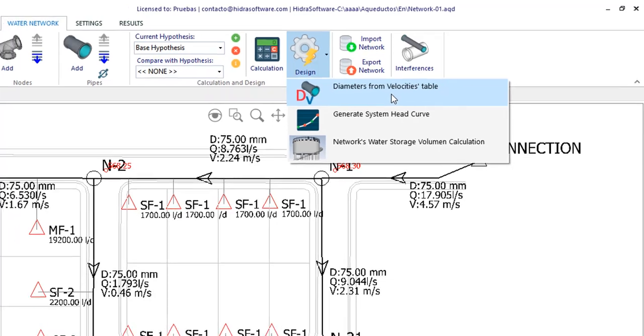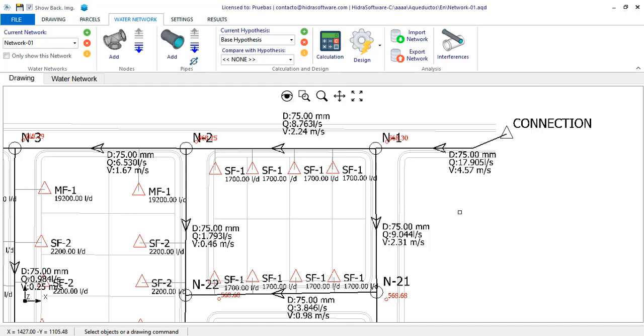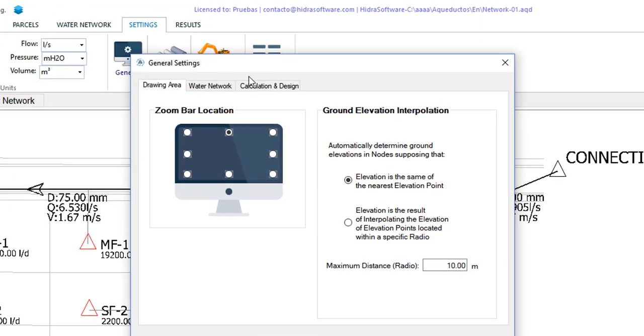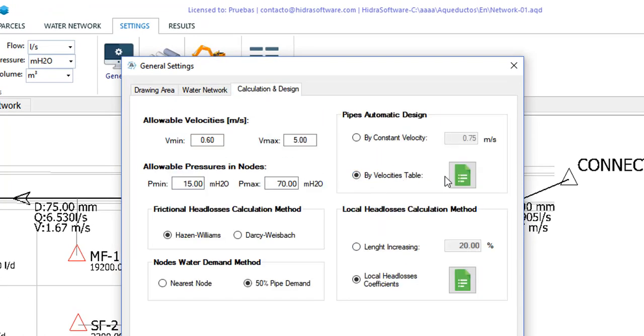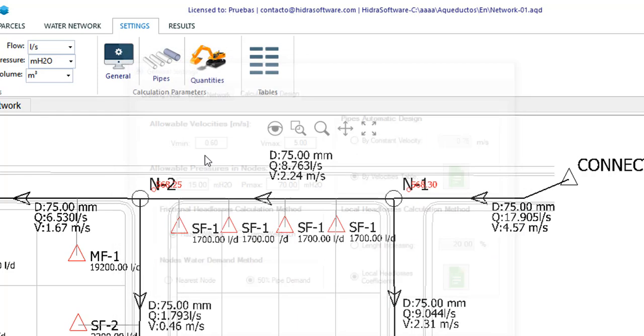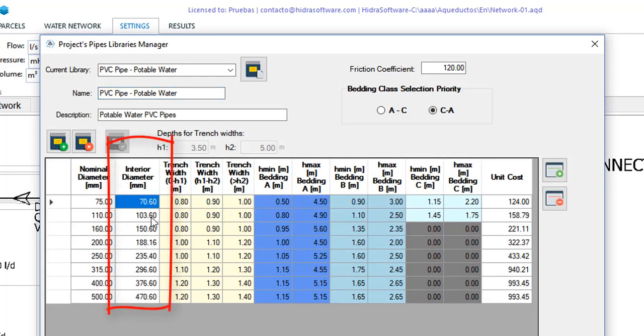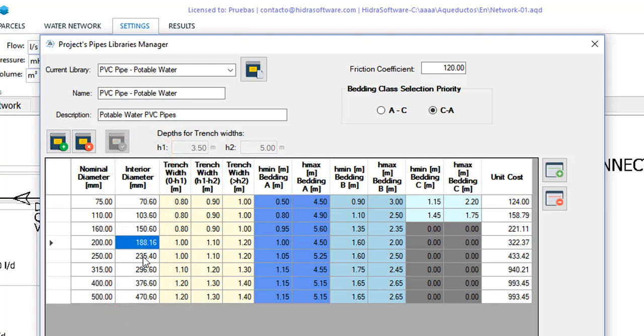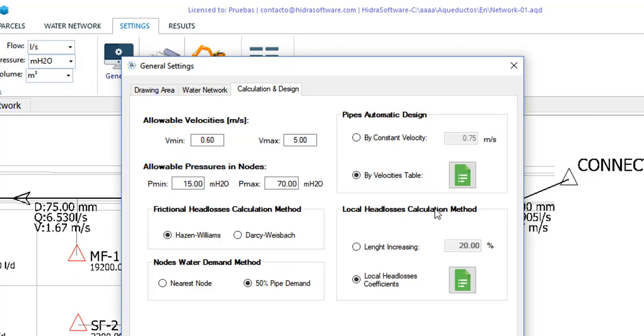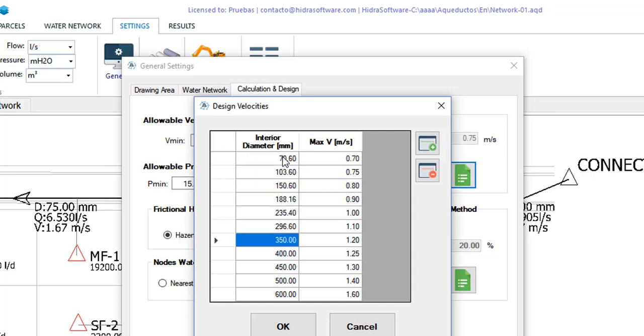In this case, let's go back to the general settings. The option of finding the diameter for a fixed velocity is available, but the chosen one is the option of selecting diameters based on a maximum velocity in accordance to values in this table. The important thing here is that we must indicate the internal diameters that are available in the pipe library we are using in the project. As we see here. So I will quickly make the modification, deleting the unavailable sizes in the library from the velocities table. Remember, the software will search for the calculated diameter the one that is close to one of the diameters of the corresponding pipe library.